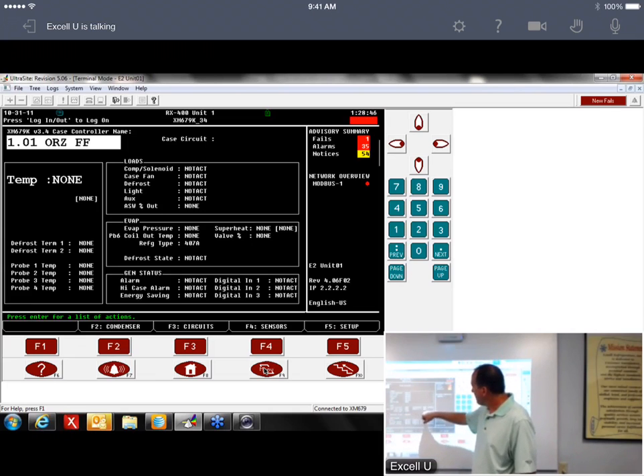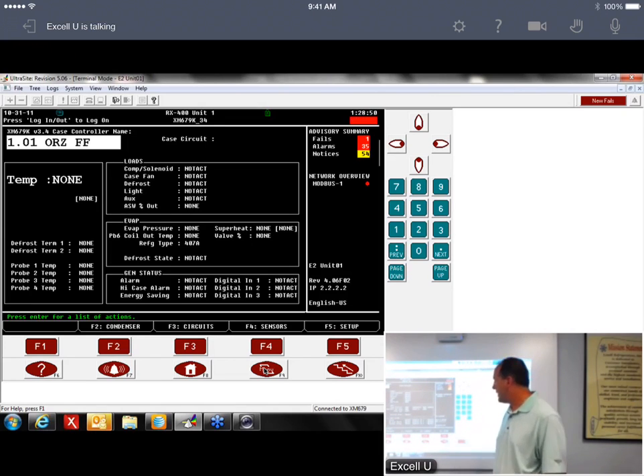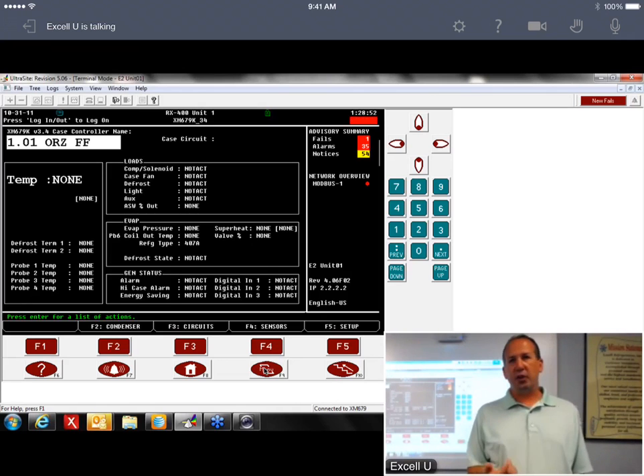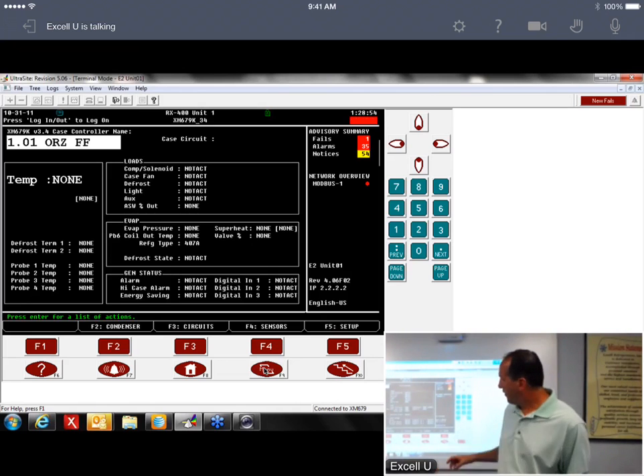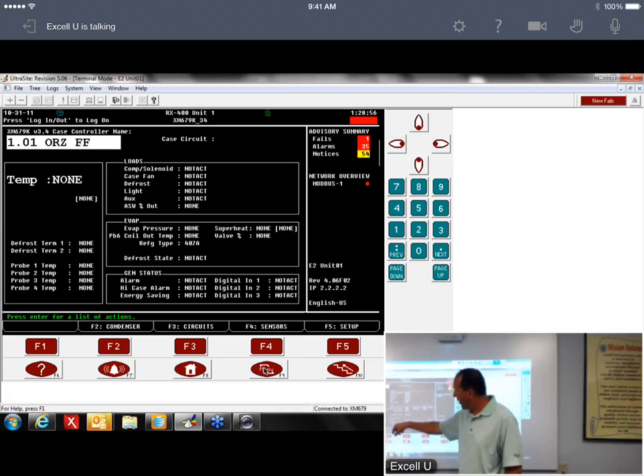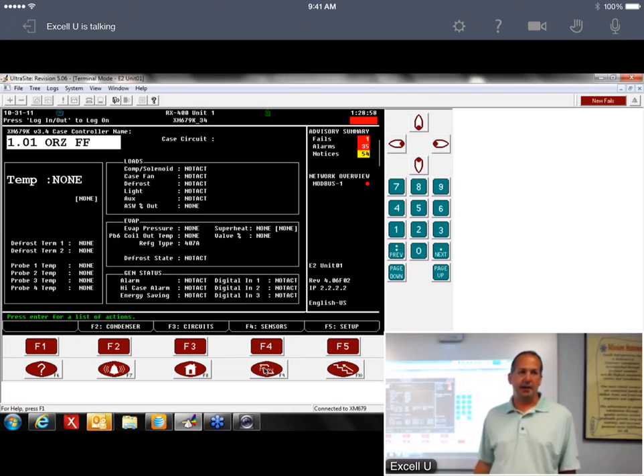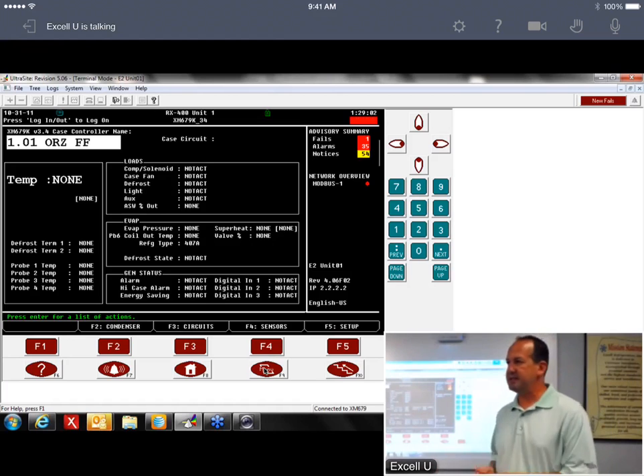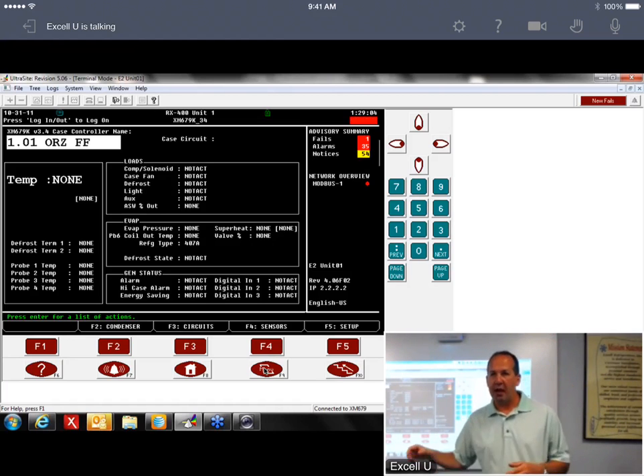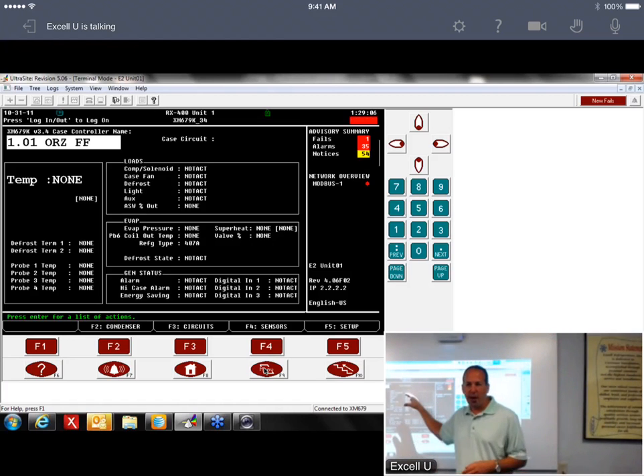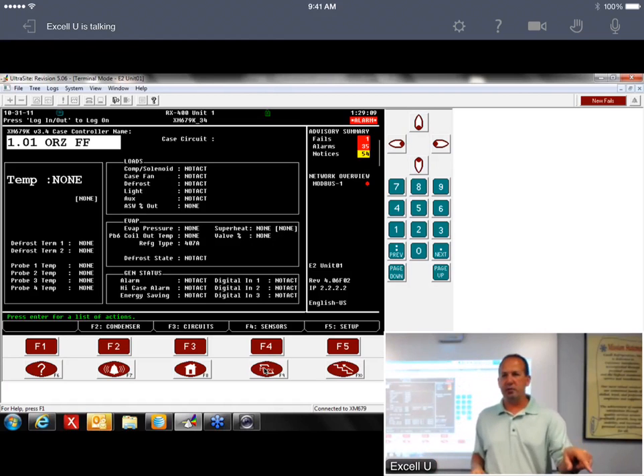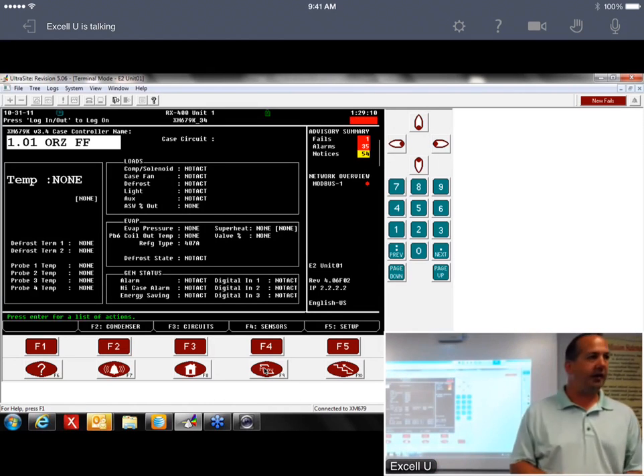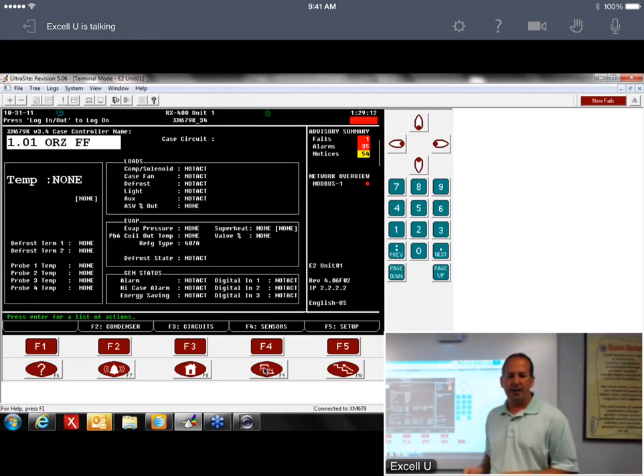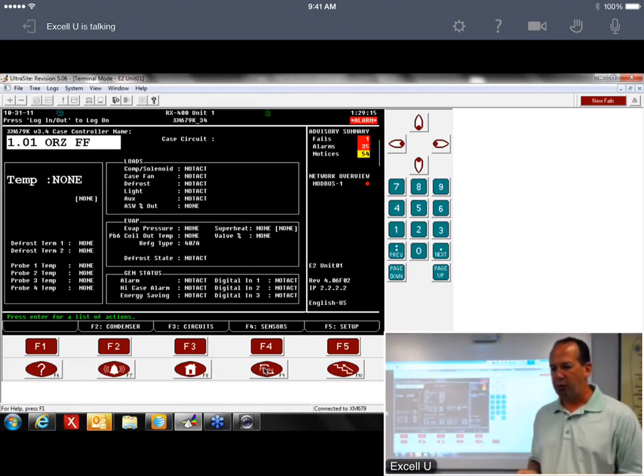Over here it'll tell you your valve percentage and also your superheat. Whenever you bring one of these online, the first thing I'd do is make sure all these temperatures populate. That's the most important piece - once you see these temperatures starting to populate, you know the parameters in this device are correct. So we'll get through that part.